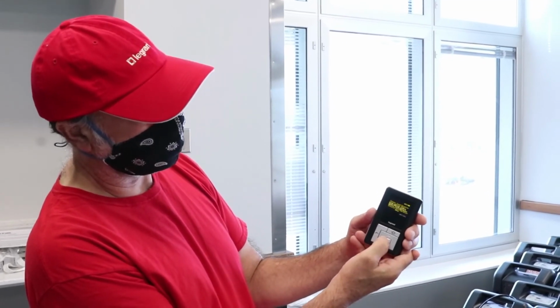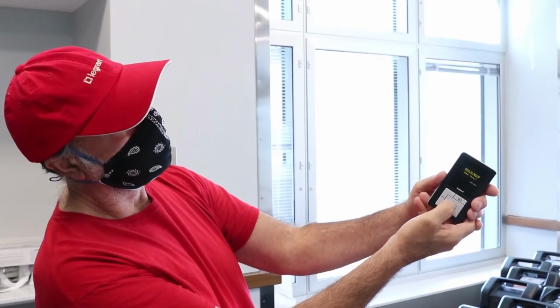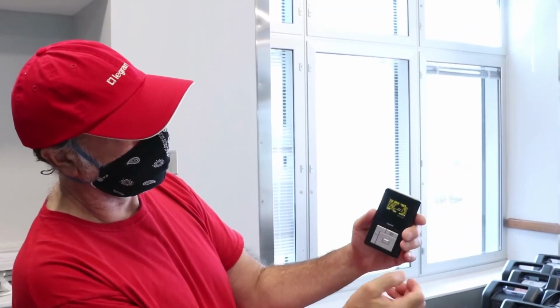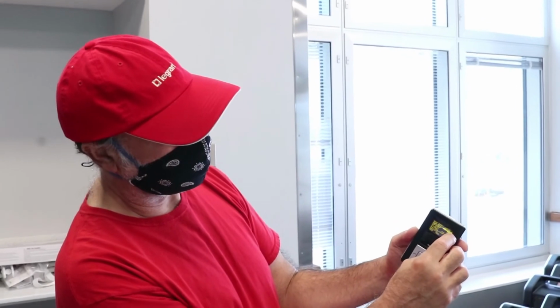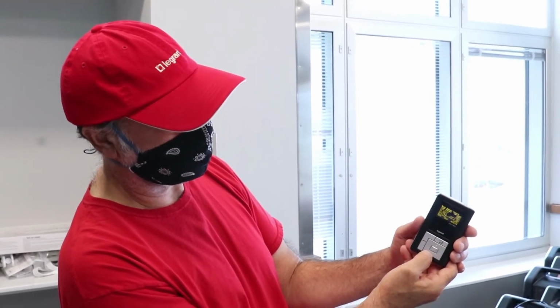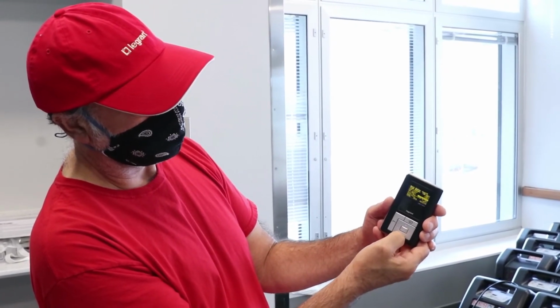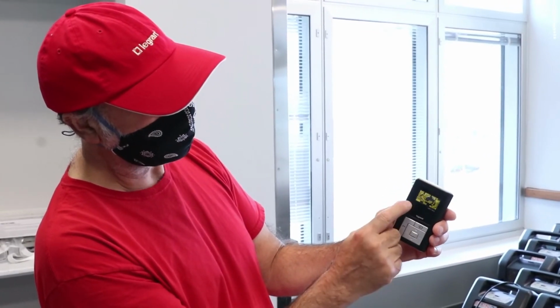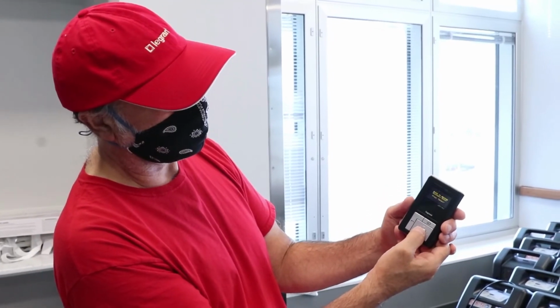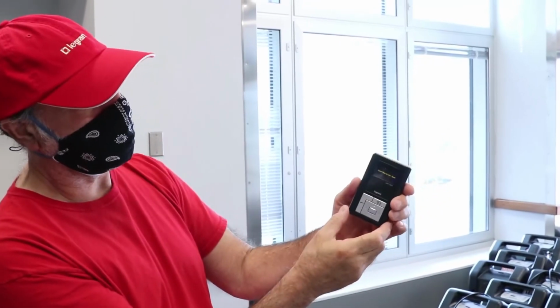So if I go back again and look at that sensor and hit current settings, it comes back. We still have our 20 minutes, our 90%, and our ultrasonic is now 50%. So I'm going to change it one more time back to 70. So I went down with the arrow to move the cursor, over 60, over 70, down, down, down, to send. Hit send, and it says configuration sent.